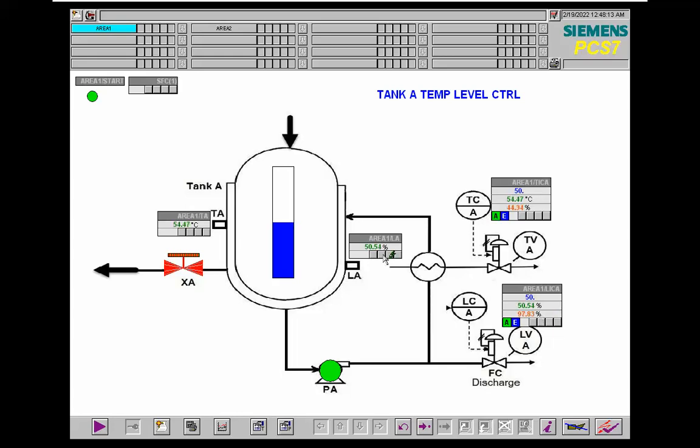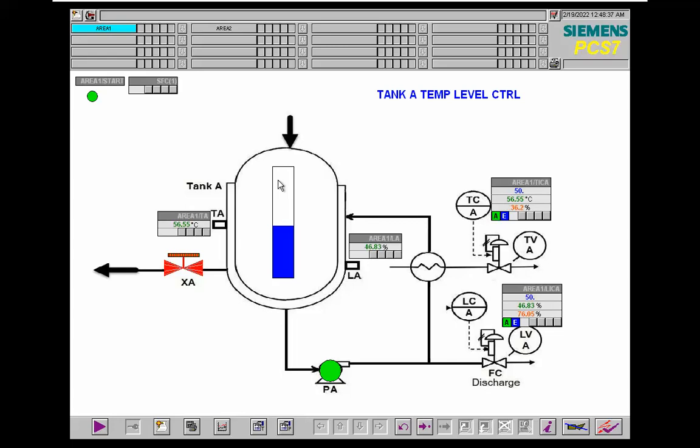In order to go to the next step, we will monitor the steady state error signal. When the error signal is in a certain window, we will move to the next part. It means that the level and temperature of this tank is maintained. It may take several time to reach the set values. When we reach the set values, XA will be true and it will be energized.